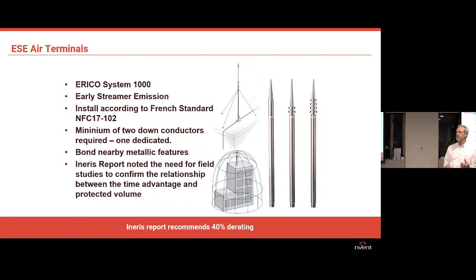As it happens, there are so many manufacturers, nobody's prepared to pay for an independent report, and one has never been done. But this lightning protection method promises, you put one up in a huge building and it promises the whole building to be protected. If you'd like to put your faith in that, it's a lot cheaper to buy one of these than other methods often. So they're certainly going in, but I'd be wary. And if you do have a serious lightning protection requirement, certainly pay close attention as to whether you would recommend or whether you'd use one of these. There are a number installed around New Zealand now.